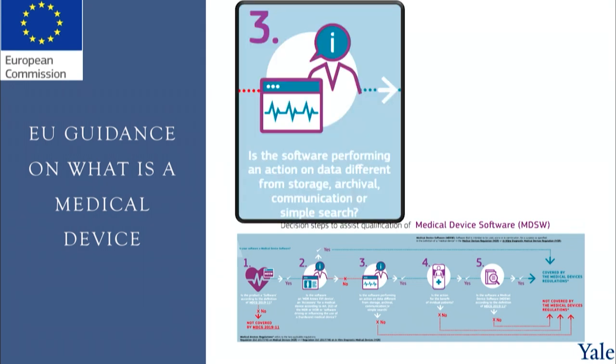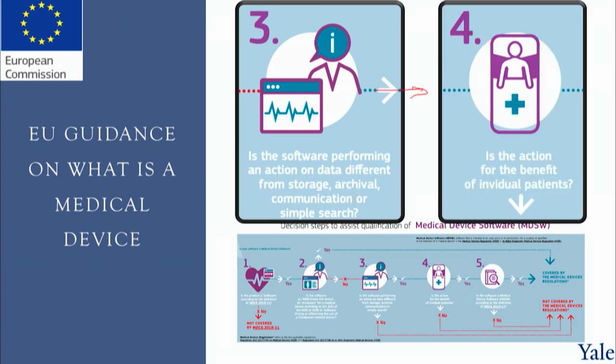So in step 3, we ask, is a software performing an action on data different from storage, archival, communication, or simple search? If it's doing this thing, it's not a medical device. If it's doing something different, then we move on to step 4, which says, is the action for the benefit of individual patients? If this is yes, now we may be meeting the definition of a medical device.